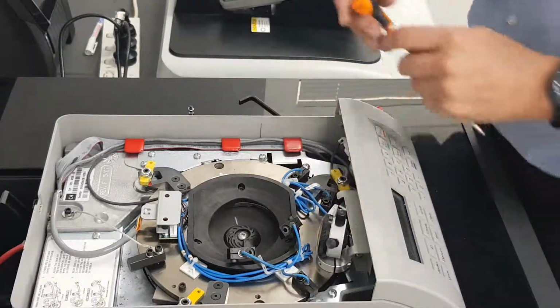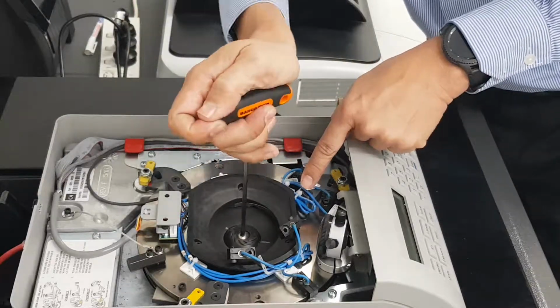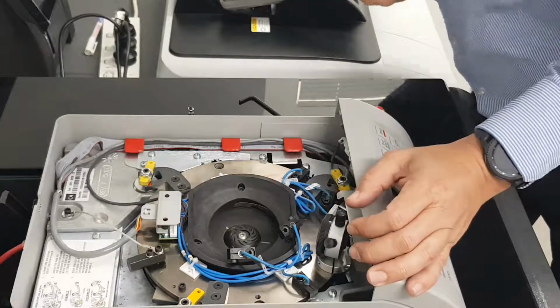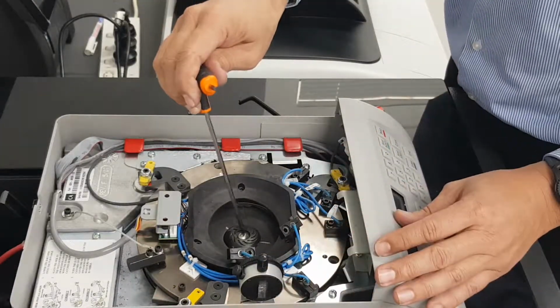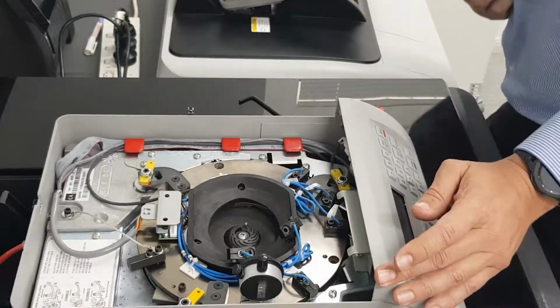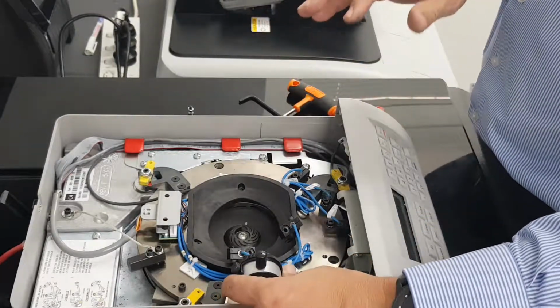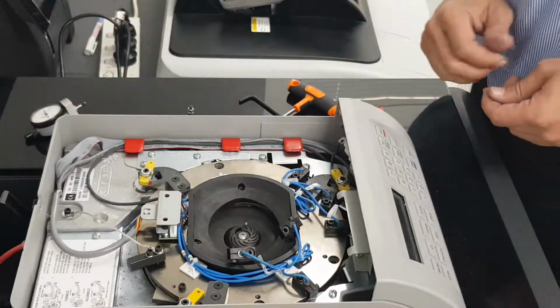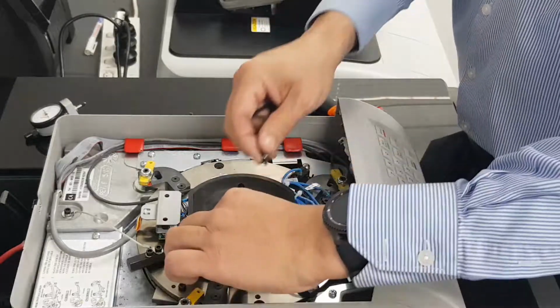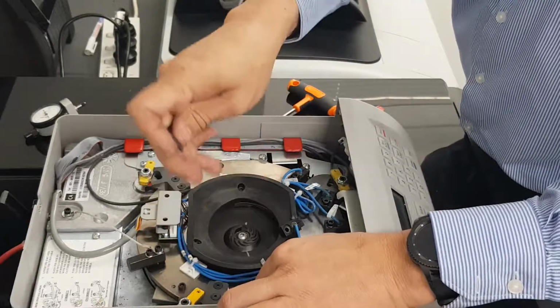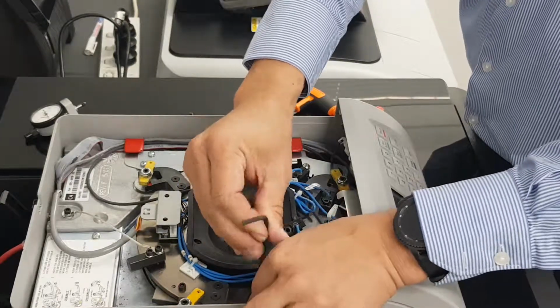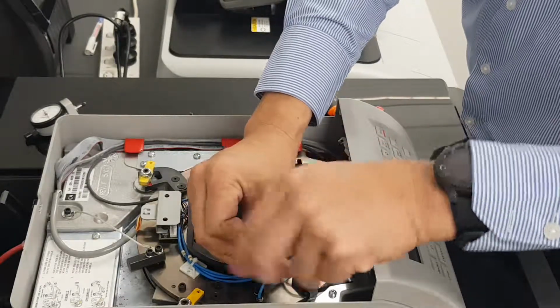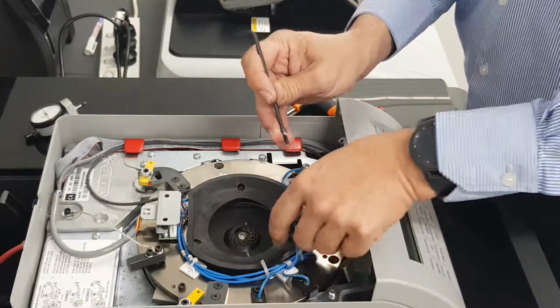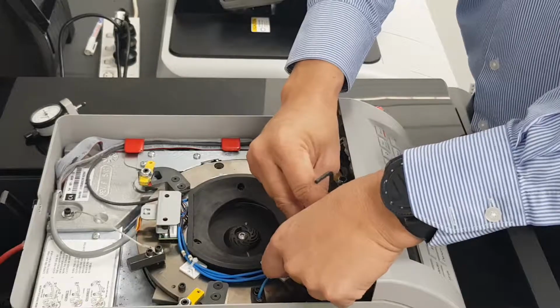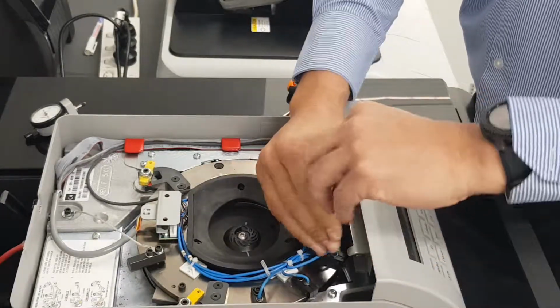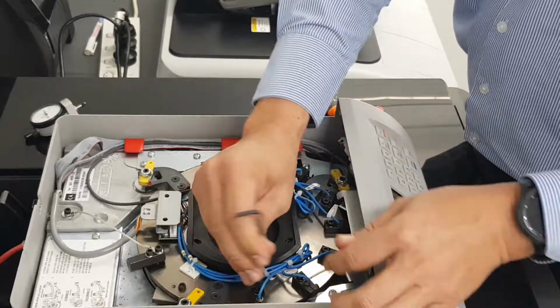Yep. Check this other point. So again, moving our high point around to line up with that sensor. Yep, 002, happy with that. Around to our last point again. Moving our high point around. Yep, perfect. So I'm really happy with that. They're all consistent now after I've made those adjustments. So what we can do then is just pop back in our sensors. Again, just be careful with these, you don't want to damage them. Last one's in, and that's pretty much it.